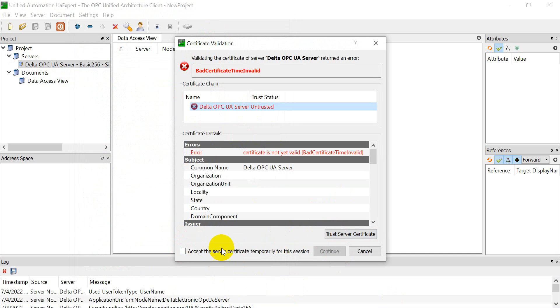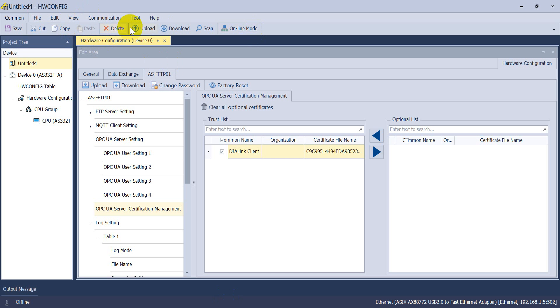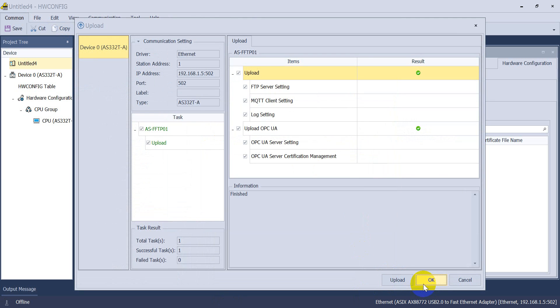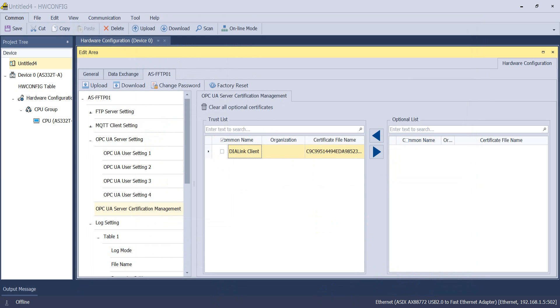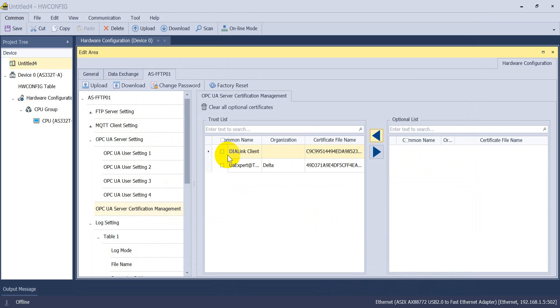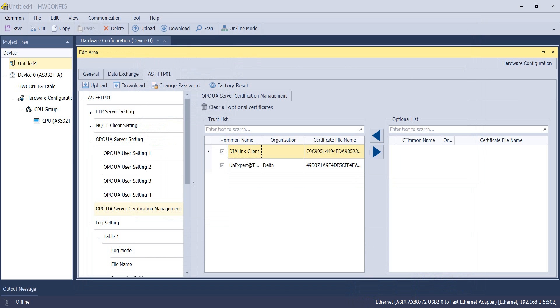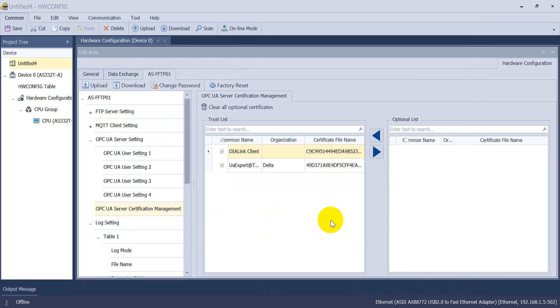Click Trust Server Certificate in UA Expert. Then go back to hardware config and upload the settings again — click OK. Add the UA Expert certificate to the trust list. Again, wait until the MS indicator becomes continuous on with green light.